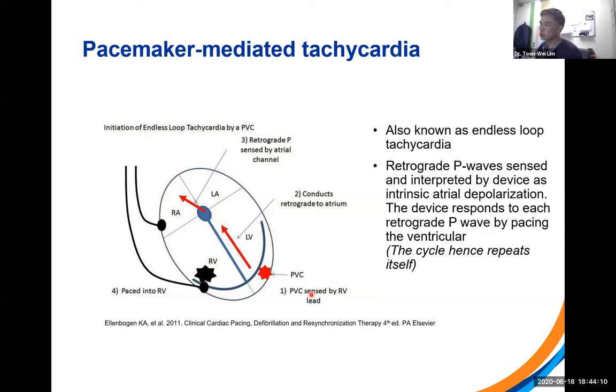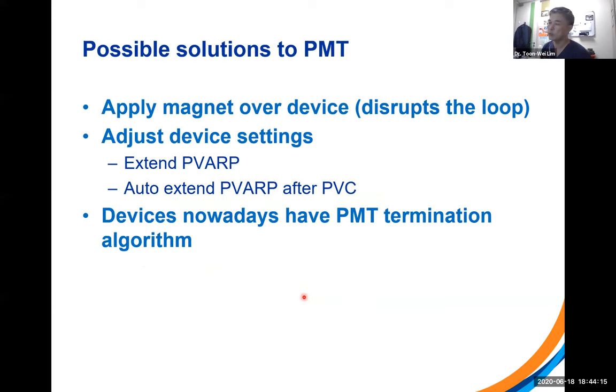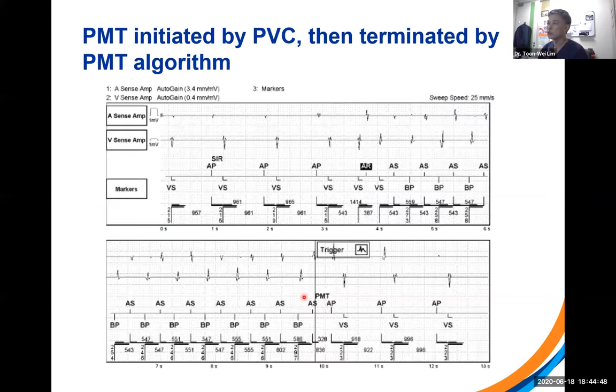As was mentioned by Professor Mon, this used to be a real problem, but these days there are algorithms that deal with it, and there are a few ways to do that. One way is to put a magnet over the device, which disrupts the loop. Another way is to extend the PVARP, which causes the sensed A to fall into a refractory period and no longer be sensed. Modern devices also have the ability to extend the PVARP after a PVC. So if it senses a PVC, it can automatically extend the PVARP and help you inhibit PMT. And of course, there are also what we call PMT algorithms, which is this.